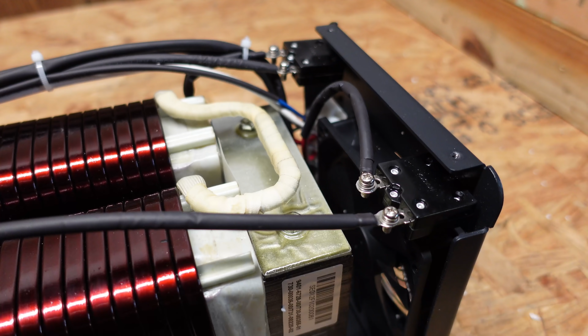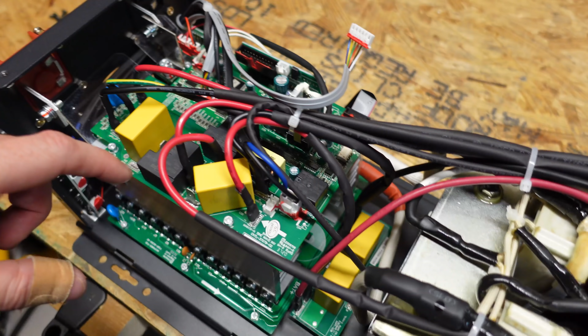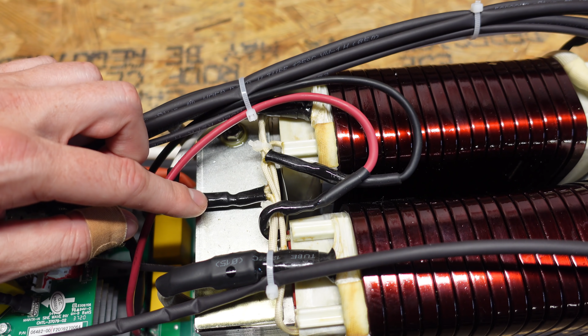That neutral wire comes back over to here and goes into this transformer. This transformer is also fed by AC input. I guess depending on these two relays here appear to be the transfer switch. So I think what it's doing, because it only takes a leg 1 and a leg 2, it must be using this transformer internally as sort of an auto transformer and generating this neutral.